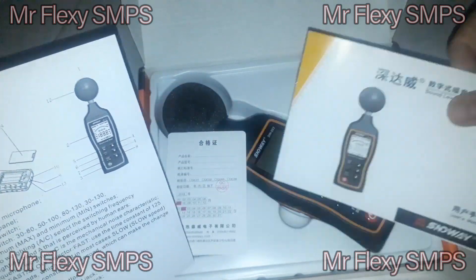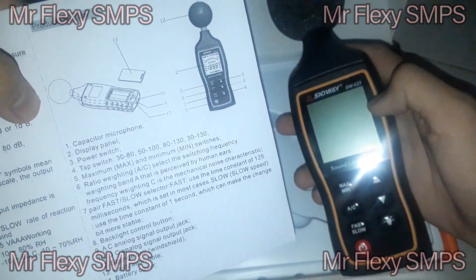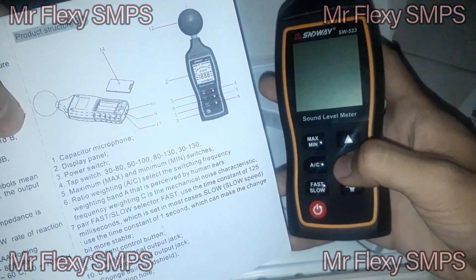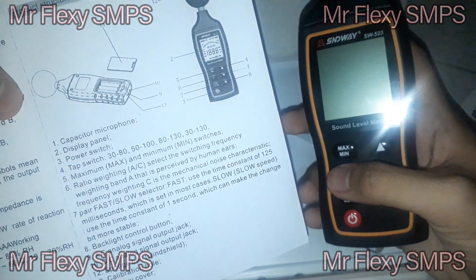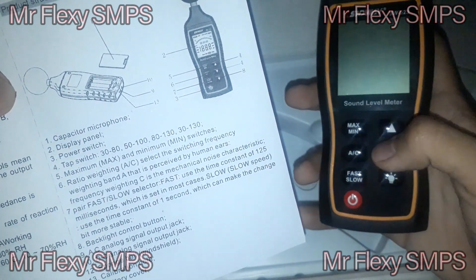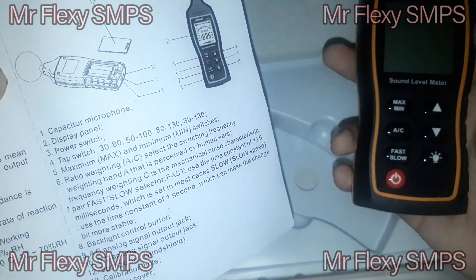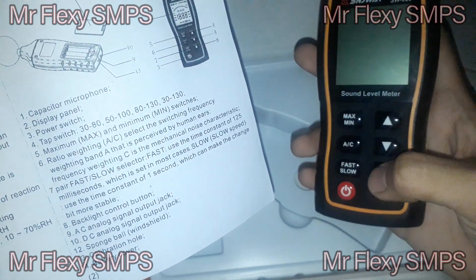The capacitor microphone can be found on the top of the device — you can see it here on the back edge. At the top we have the capacitor microphone, then the display panel, a power switch, and a tap switch for the range selection between 30 to 80 or 50 to 130 dB. We also have a frequency weighting switch for A or C mode — A-weighting is what is received by human ears, while C-weighting is for mechanical noise. There's also a fast/slow switch; fast uses a time constant of 125 milliseconds and slow uses one second, making readings more stable. There's also a backlight button.